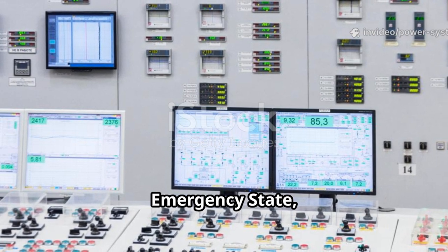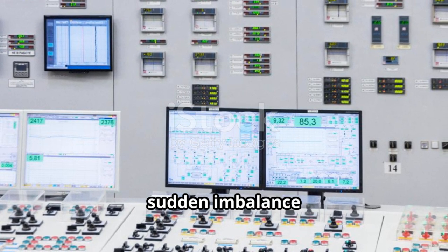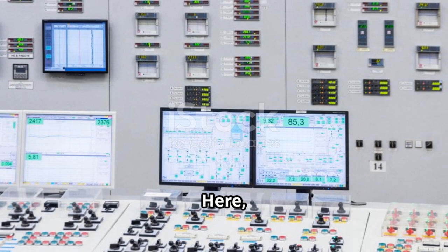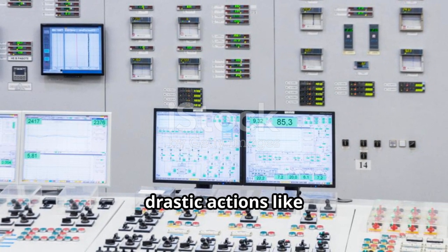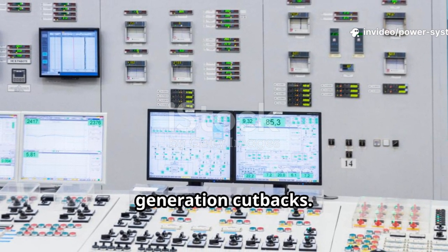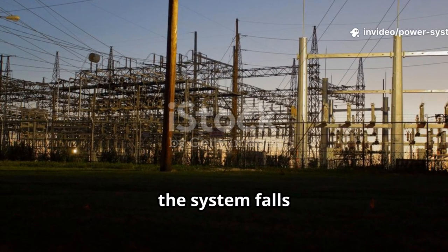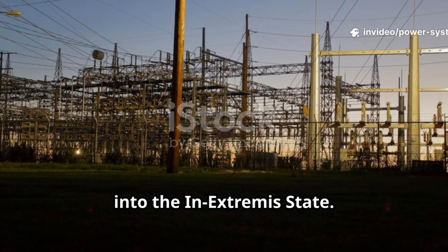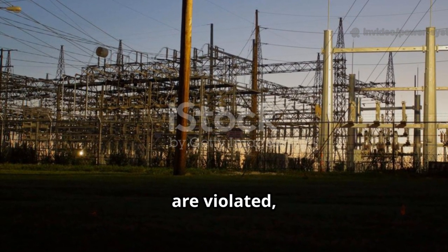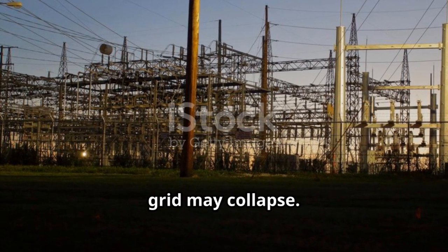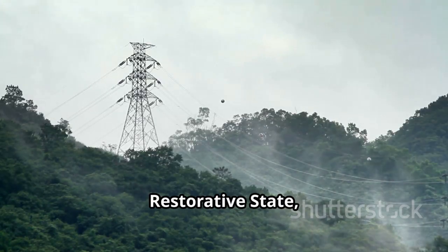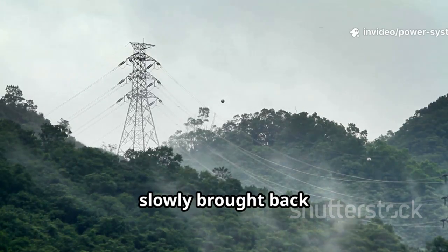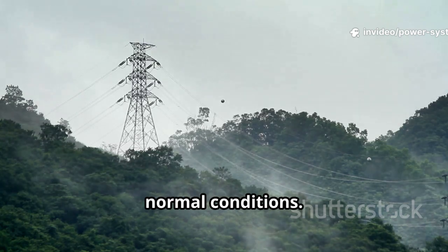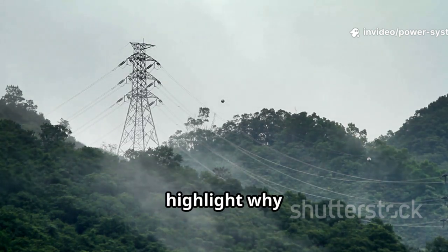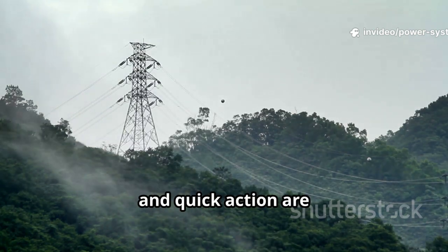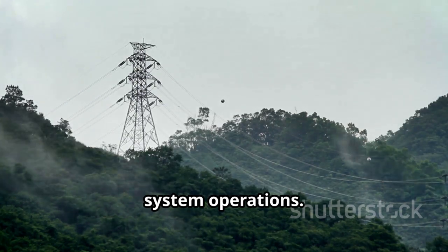Next is the emergency state, often caused by sudden imbalance between generation and demand. Here, operators may need drastic actions like load shedding or generation cutbacks. If things worsen, the system falls into the in extremis state. Both generation and demand constraints are violated, and parts of the grid may collapse. Finally, comes the restorative state, where the system is slowly brought back to either alert or normal conditions. These states highlight why constant monitoring and quick action are critical in power system operations.